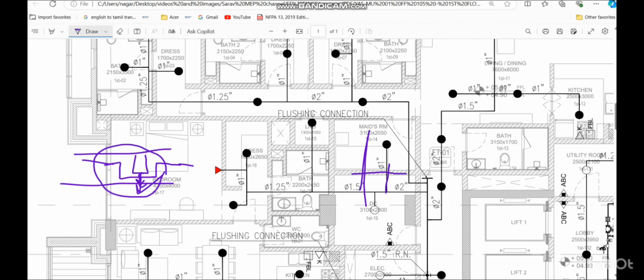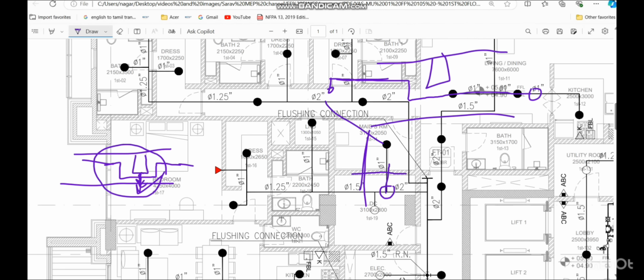So the question will come then, how to resolve this one, because we don't have the space. So for this type of thing, what you can do is, let's consider the same thing. You have the slab, you have the column, and you have the ceiling here. So here at this point, where it is connecting with the main branch, you are taking the line like this. Here you have the sprinkler. What you have to do, if you are taking down, then you have to continue the same way till the line. You should not take it up. So if you take it up, again auxiliary drain will have to provide. So instead of that, you can continue straight line and you can connect with the line. So this is normally a very good type of installation.